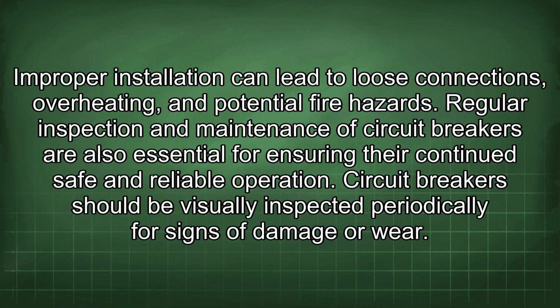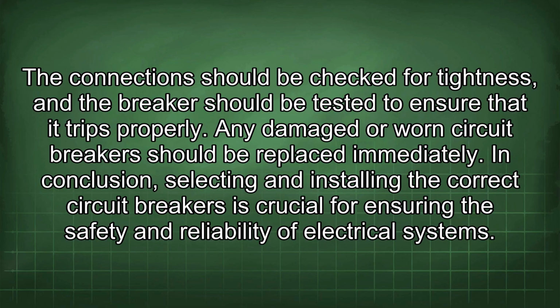Regular inspection and maintenance of circuit breakers are also essential for ensuring their continued safe and reliable operation. Circuit breakers should be visually inspected periodically for signs of damage or wear. The connections should be checked for tightness, and the breaker should be tested to ensure that it trips properly. Any damaged or worn circuit breakers should be replaced immediately.